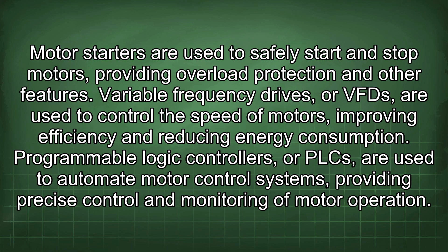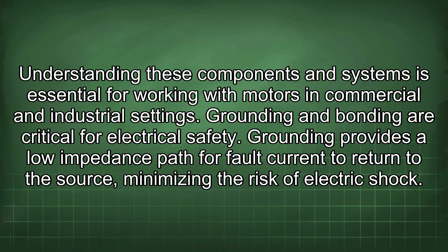Grounding and bonding are critical for electrical safety. Grounding provides a low impedance path for fault current to return to the source, minimizing the risk of electric shock. Bonding ensures that all metal parts of an electrical system are electrically connected, preventing voltage differences that could create a shock hazard. The NEC provides detailed requirements for grounding and bonding, which must be followed carefully to ensure safety.